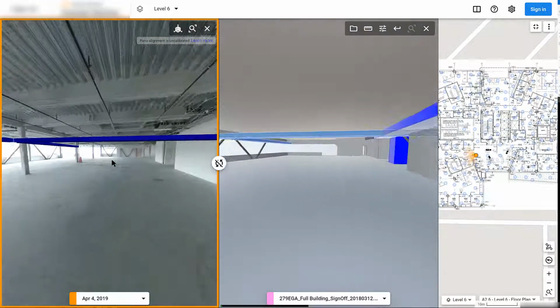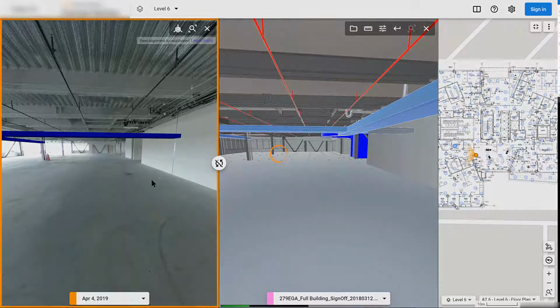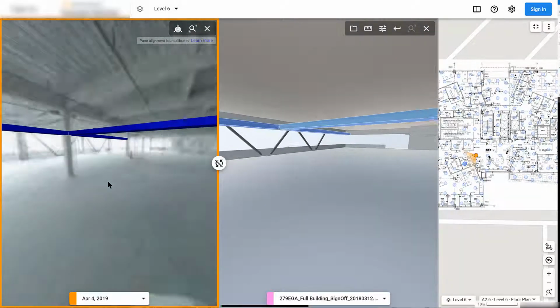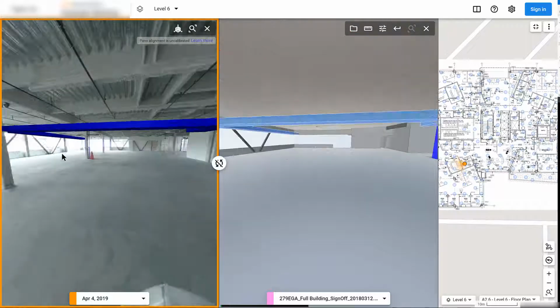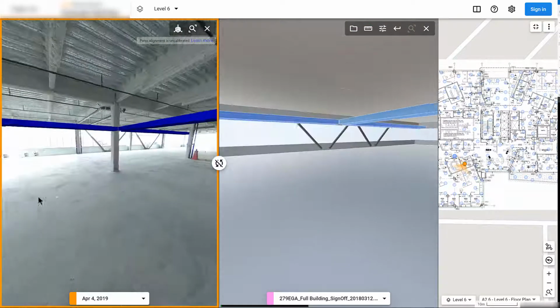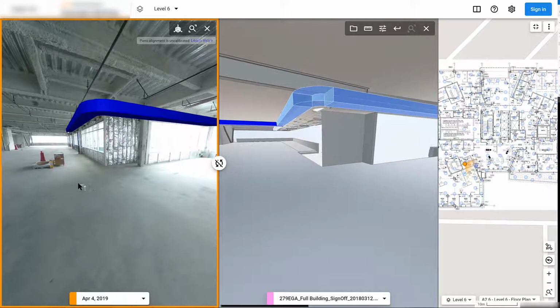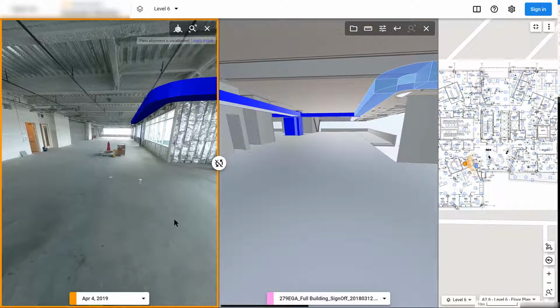So that's kind of what it looks like compared to the design, and I can add any other additional pieces I want to show here as well, pretty straightforward. So as that generates, that's something we can walk around and inspect and see if it does not match up with sprinkler systems, so doing a little bit of that inspection to see how that's going to lay out or if there's any design issues that are not being met right at this point.